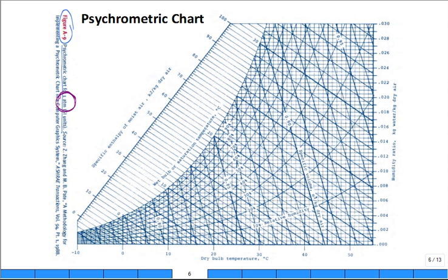If you do any design work at a mile-high city like Denver or parts of Albuquerque, or even some other cities that are more than a mile high, you have to get high-altitude psychrometric charts. Or, hey, there's a thing called a computer, and it's been invented since then, and there's a lot of software that can calculate things and then have it plotted in a psychrometric chart for whatever elevation you want to work with. But don't worry, we're at 1,000 feet here. We're far from a mile-high elevation, and it's going to work really well. So when you take a look at the chart, what's on the x-axis?